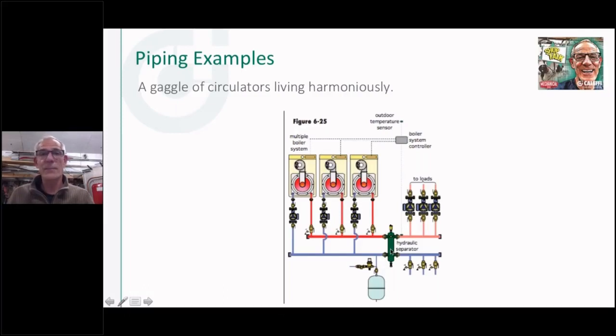You've got to have that separation of some sort. And it's either closely spaced tees on every one of these, closely spaced tees on this, or throw a separator in there. I've got perfect air removal because I've got my air removal at the very hottest point in my system, coming right out of my boiler. I've got my dirt separation at the best spot. I'm going to catch my dirt coming back before it gets into my pumps, before it gets into my system. Got my magnetic function. And there's my expansion tank connection. Everything. It doesn't get any better than that.